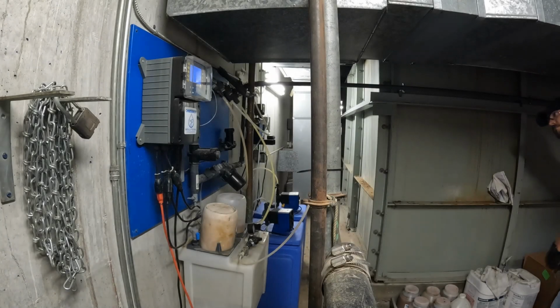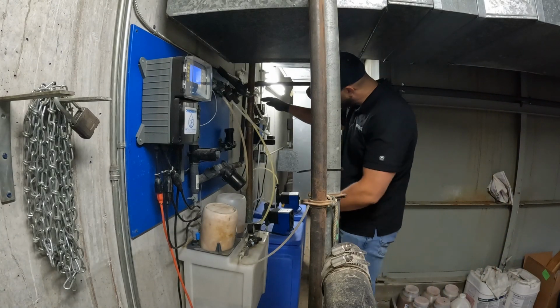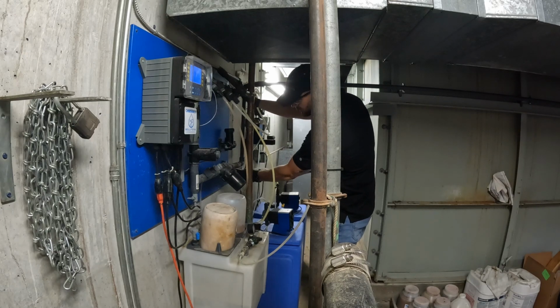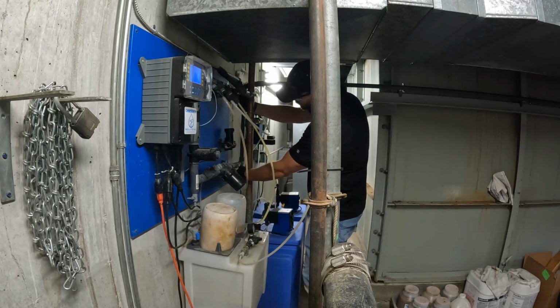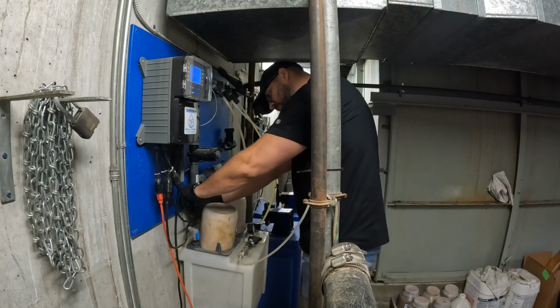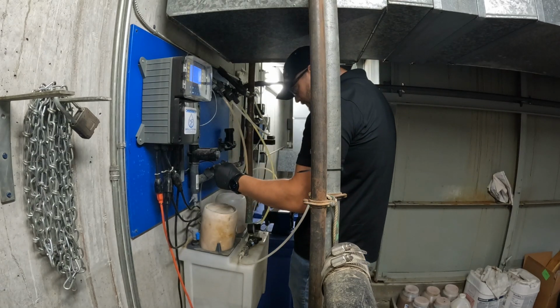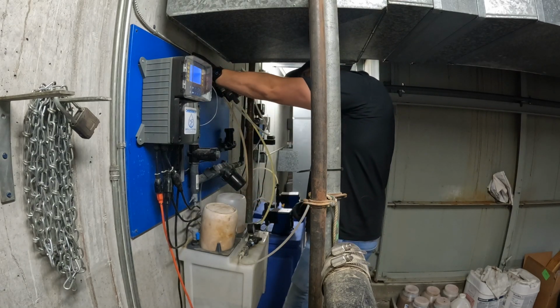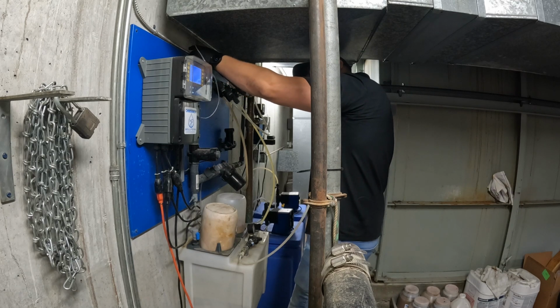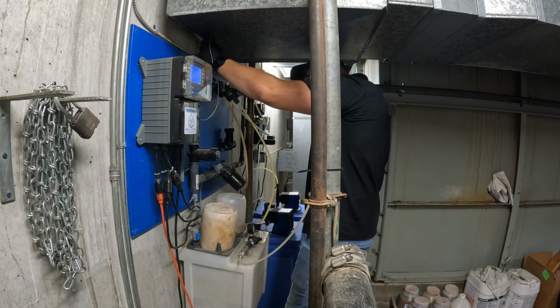Now let's take a look at cleaning up some of the probes and sensors on the manifold. Your first step will be to shut off the flow to the manifold using the ball valves. Slowly close both valves and release pressure using the sample nozzle. Always be sure to use a drain, a cup, or a bucket to avoid water on the floor. This particular system has a floor drain directly under the manifold.